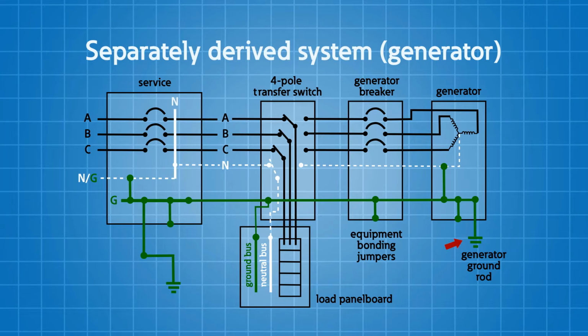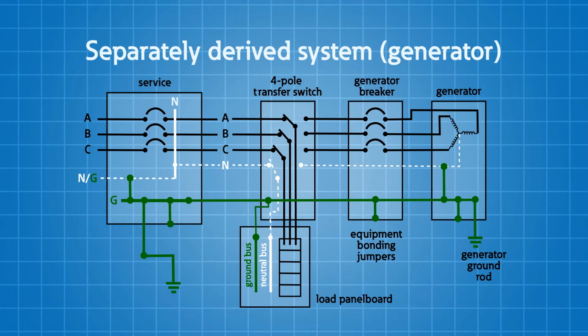And if we look over at a generator, you'll typically see people drive a ground rod next to a generator, and they'll bond the enclosure of that generator with that ground rod. If they connect the neutral to that enclosure inside the generator, they're establishing a separately derived system. Now, why is it important to understand that action will create a separately derived system? Because it will drive what you do in the transfer switch. If you bond that neutral to ground in the generator and you establish a separately derived system, you're going to need to switch the neutral in the transfer switch. That would mean you would need a 4-pole transfer switch instead of a 3-pole transfer switch.